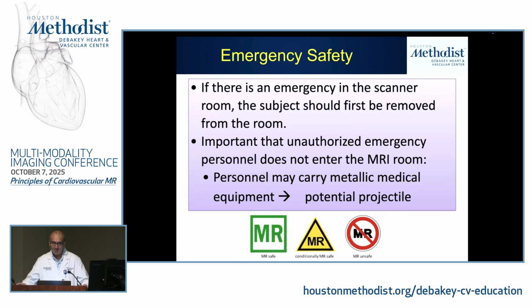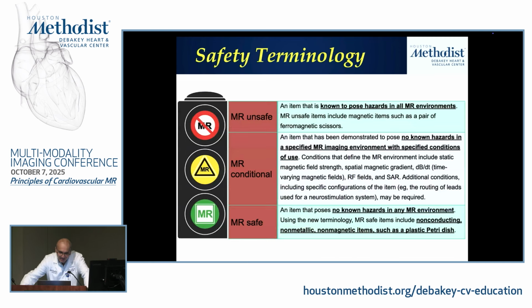Next, let's talk about terminology. People always like to ask me, hey, is this MRI safe, is this MRI unsafe? That used to be an old nomenclature that we used to have. Nowadays, the FDA uses a tripartite nomenclature. There's MRI unsafe, MRI safe, and MRI conditional, okay?